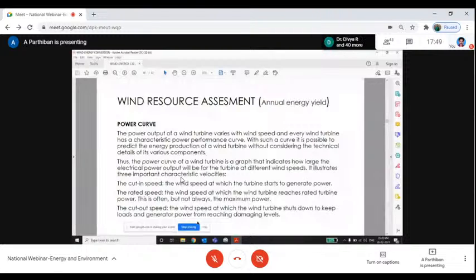The third one is the cutout speed. Cutout speed is for safety purposes, because after 20 or 25 meter per second, there is high wind during the monsoon season or any high pressure season. At that time, it crosses 25-30 meter, and there may be some damage to the blade, or the wind turbine can fall. So for safety, there is a cutout speed. During the cutout speed, the wind turbine will stop producing energy. These are the three things in the power curve: cut-in speed, rated speed, and cutout speed.